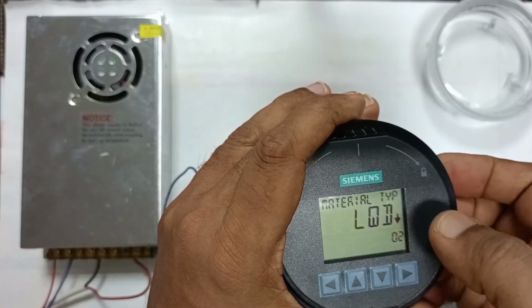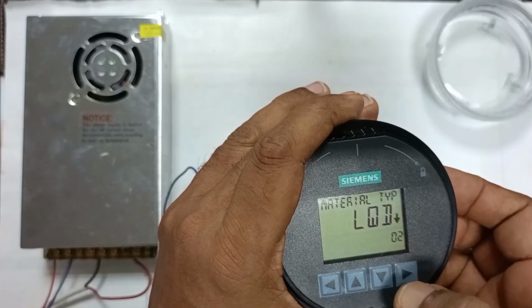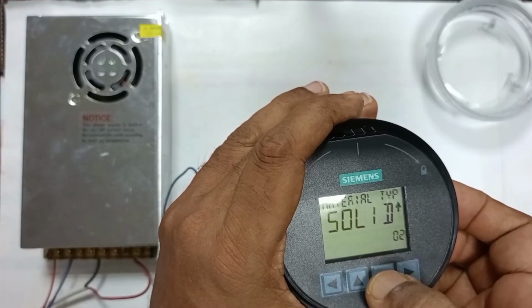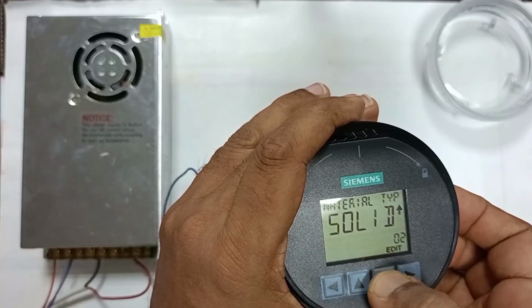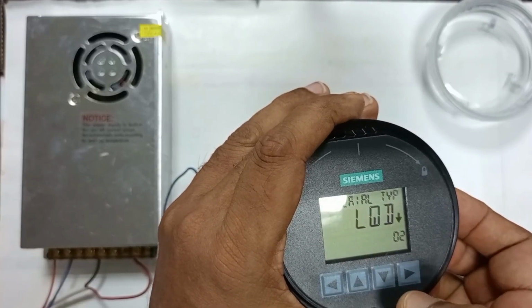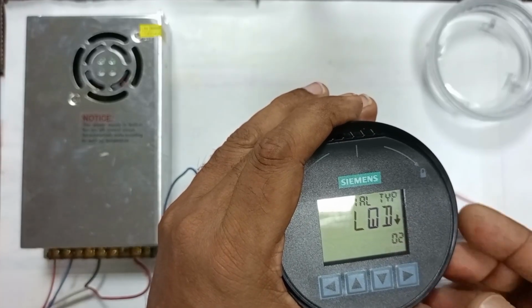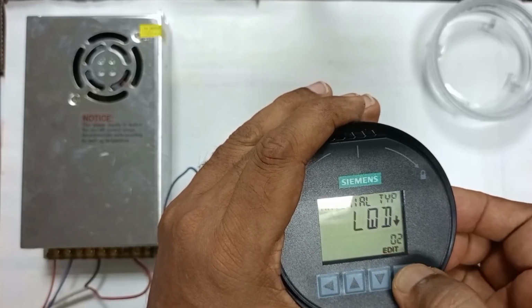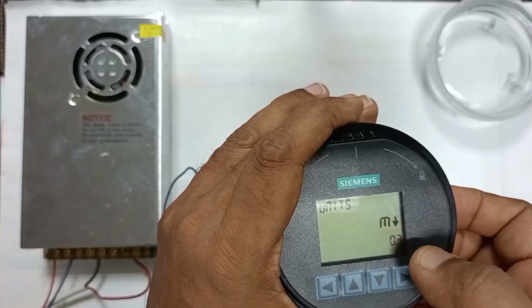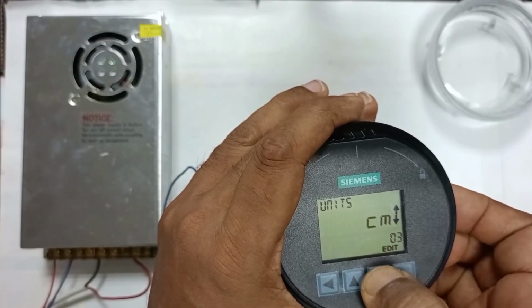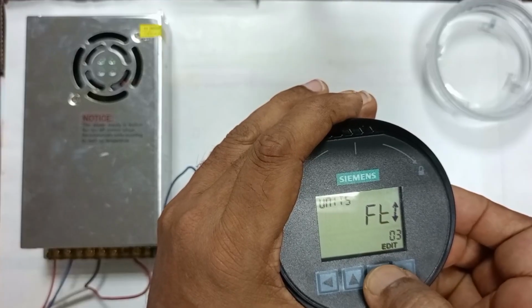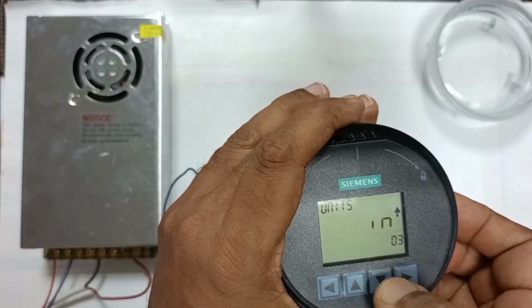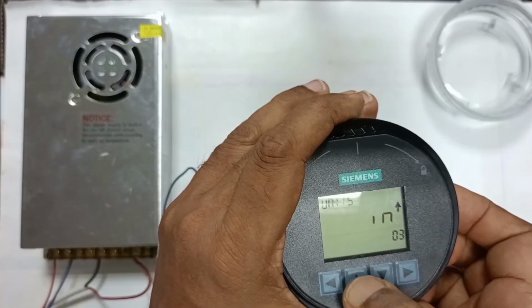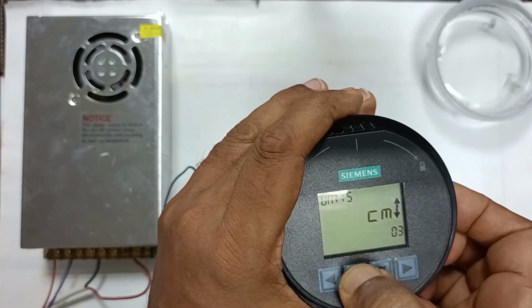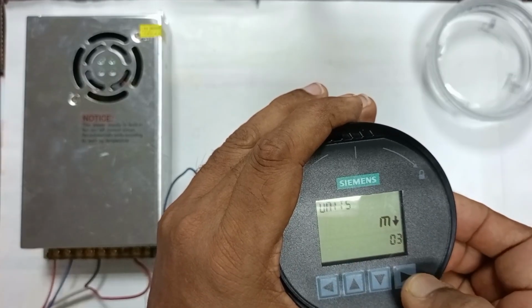Okay, material type liquid, LQD. Here is also downward. If we press, then here is solid and liquid. If we press upper again, you see here is liquid. As we use this transmitter for measuring the liquid level, we will press enter here. Okay, it is selected. Units, also meter. Here is centimeter, millimeter, and this is another thing, inch. So if we press upper side, we will measure the level in meter units. So we press here.